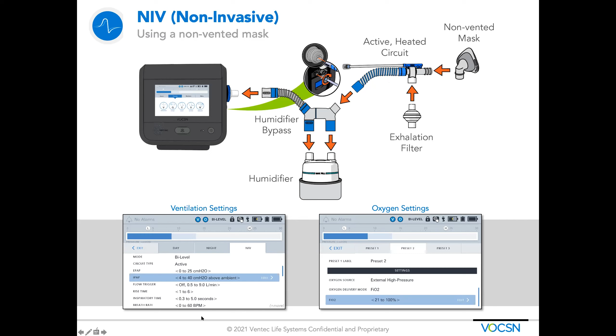There's a single tube that goes back from the circuit. These two ports are to the pneumotach at the airway, and this port is for airway pressure and the exhalation valve, and the filter goes on here to prevent contamination of the room. And then finally, if you want to use it in an intubated patient, it's a similar look at the circuit, an active heated circuit connected to an endotracheal tube.